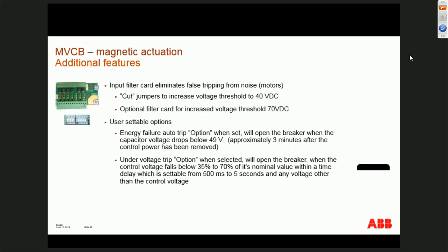So it's customer requirements that drive that. Also, under voltage trip works exactly as it would on a spring charge type breaker, where you have a separate under voltage input. That voltage can be totally separate from your control input voltage. You would set this voltage by some dip switches that are on the filter card itself, and you can also set it for a specific time delay from half a second to 1 second all the way up to 5 seconds.